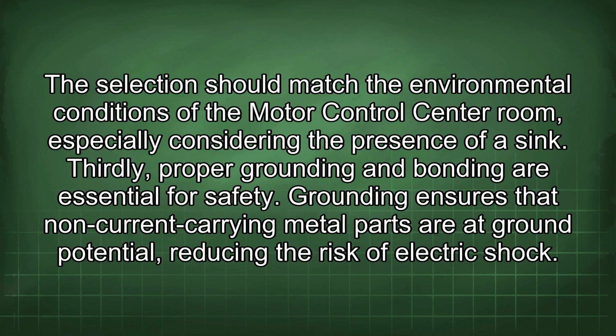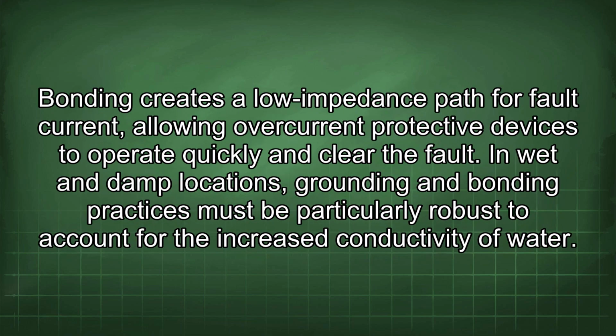Thirdly, proper grounding and bonding are essential for safety. Grounding ensures that non-current carrying metal parts are at ground potential, reducing the risk of electric shock. Bonding creates a low impedance path for fault current, allowing overcurrent protective devices to operate quickly and clear the fault. In wet and damp locations, grounding and bonding practices must be particularly robust to account for the increased conductivity of water.